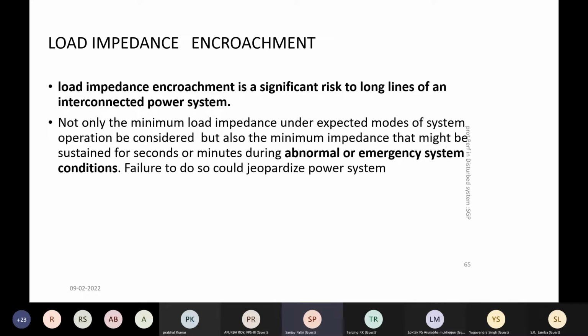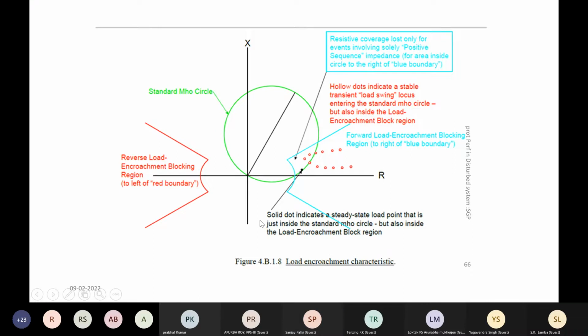The second issue is the load encroachment phenomena. The load impedance encroachment is a significant risk, as we said, due to phenomena like voltage instability or voltage collapse, which I had explained with the PV curve. And what happens is, if this is your, say, circular characteristic of the distance relay, then during this power swing condition or the short time emergency loading condition due to, say, voltage collapse during dynamic instability, the load on the line will become so high that it will cross the zone 3 characteristic of the distance relay, and then the tripping will occur.